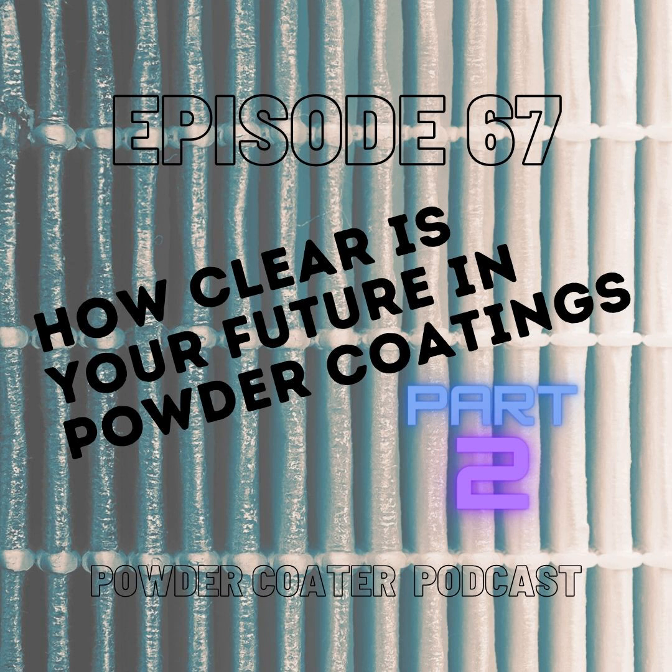And when you look at that, that's all well and good. That's a very efficient way to heat a lot of water because you have a lot of surface area, as long as you're cleaning your tank from your sludge, which is a whole other issue. That's where maintenance comes in, because if people aren't maintaining their washers and you have sludge buildup, you're going to burn out your tube, and then you've got a whole hot mess. Or you don't have a hot mess, you have a cold mess because you burned out your tube.